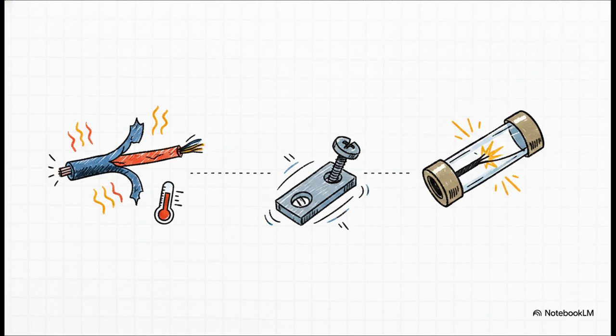Wire insulation degrades from temperature fluctuations. Physical vibrations from nearby heavy equipment can slowly shake terminal connections loose. Or it could be something as mundane as a blown fuse or a trip control voltage supply breaker instantly killing power to the trip coil. None of those things care that you had a totally successful maintenance test 3 weeks ago.